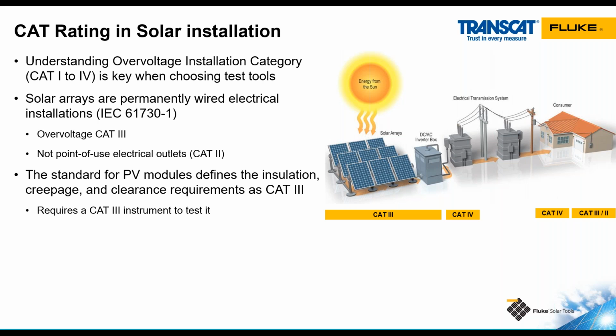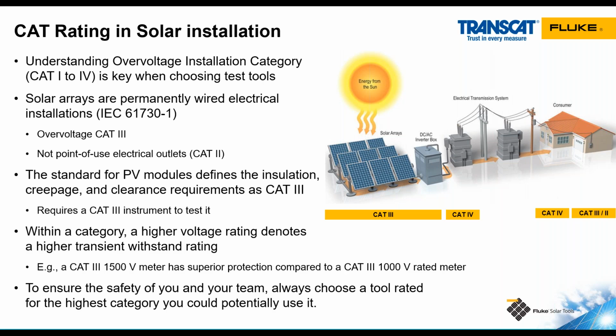When we rate our test equipment, the higher the voltage of the system we're working on and the closer we are to the potential source of transient voltage spikes, the larger the safety requirements of that tool would be. When we're looking at category ratings, a category 3 tool will have a higher transient voltage spike resistance than a category 2 tool, and category 4 higher resistance than category 3 rating tools.